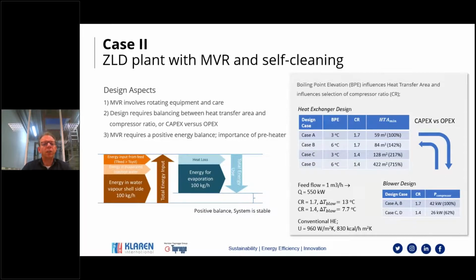The second part, which you see here also in more detail on the right side, is that in the design of an MVR, you're always balancing between heat transfer area and the compressor ratio. Heat transfer area means investment up front in material, in square meters of heat transfer area, and the compressor ratio is in fact not your investment, but your operational cost, because it will determine how much energy the compressor requires.